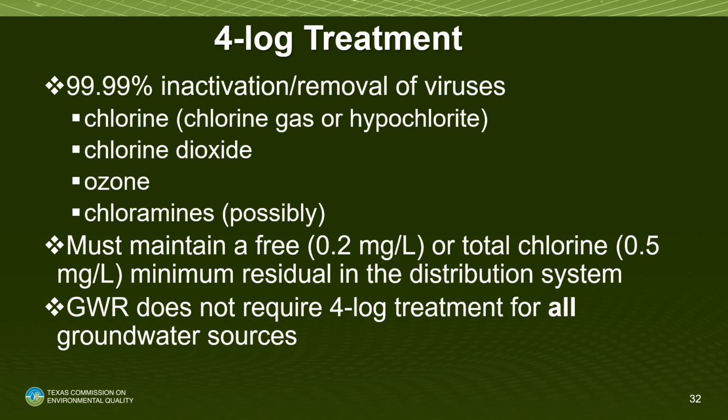I'd say free chlorine. There are other ways to get 4-log. You can use some of these other disinfectants. But in those situations, especially chloramines, that's going to require a huge amount of storage capacity to be able to get 4-log credit. There's one example of a system that got their water from like 62 miles away, and we were able to work with them on the CT study.